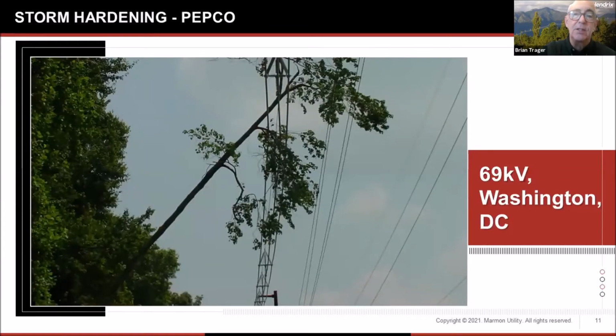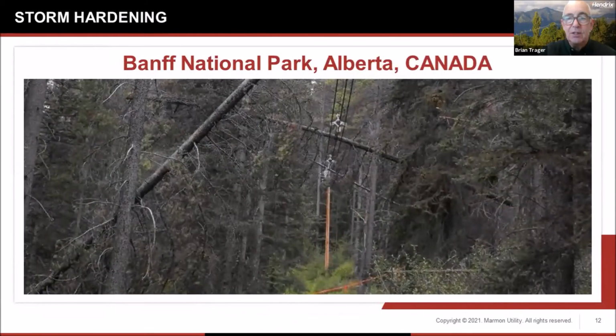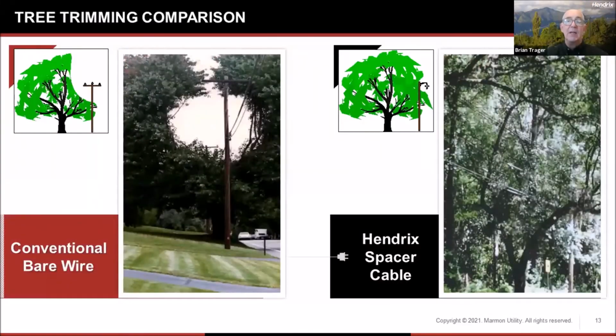Here's a tree on a 69 kV transmission line, no outage. This is one of the famous national parks in Canada, where they can go in there and in a winter, and you can see you've got 3 trees lying on the messenger for the whole winter, no outage. They go out there in the spring, take those trees off, still no outage. So that's what we want.